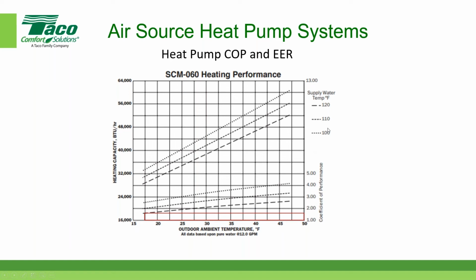If we had a supply water temperature like we showed a minute ago, 100 degrees Fahrenheit, and a 47 degree way out here, our COP would be above 4. Now, some of the manufacturers' lines are a little bit steeper and you can get COPs as high as 5 or even higher than that. So that's what it looks like graphically.